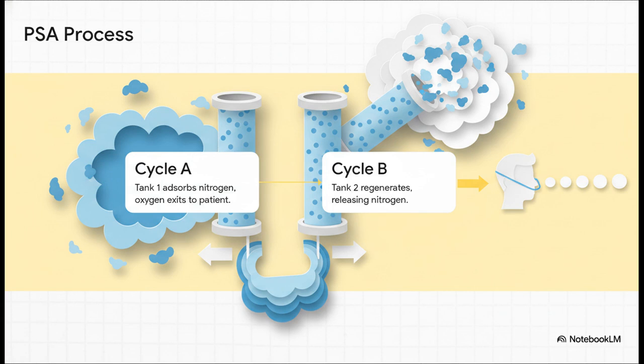Now we get to the actual soul of the concentrator. It uses a process called pressure swing adsorption. Inside the machine, there are columns filled with a specific material called zeolite, which acts literally like a microscopic molecular trap. Here's how it works. In cycle A, the machine pressurizes the first tank, and the zeolite physically traps all the nitrogen molecules, letting only the pure oxygen flow right past and out to the patient. Then, in cycle B, while the second tank takes over the oxygen delivery, that first tank depressurizes and basically exhales the trapped nitrogen safely back into the room. It just swings back and forth like this, doing this molecular sorting hundreds of times a minute.